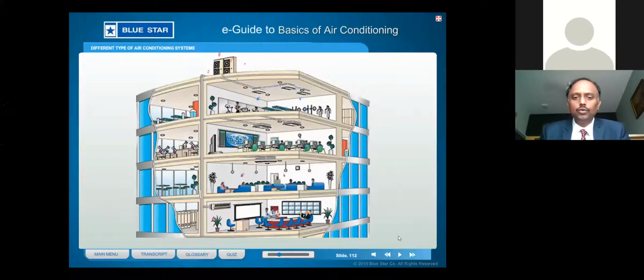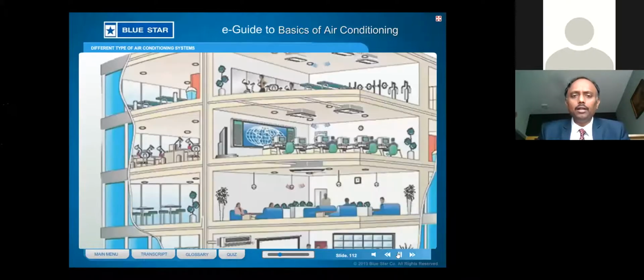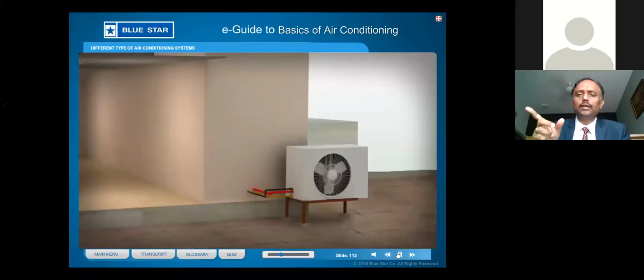Because of the electronic expansion valve, this system has the ability to read the inside load conditions very precisely. For example, one indoor unit can operate from 0 to 420 steps. Imagine a 2-tonner indoor unit operating across 420 steps - that means it can adjust in increments as fine as 0.01 to 0.02, because of the embedded electronic systems.